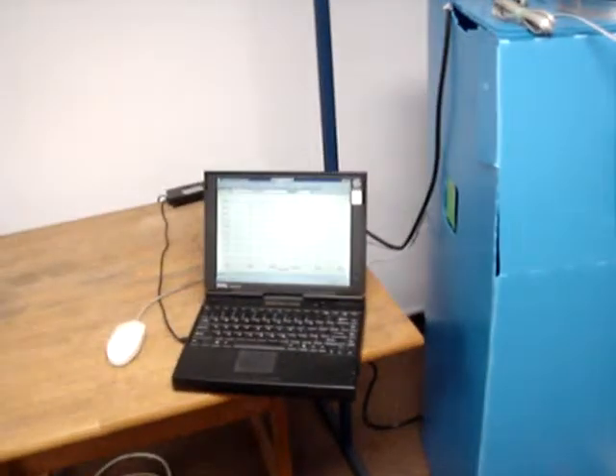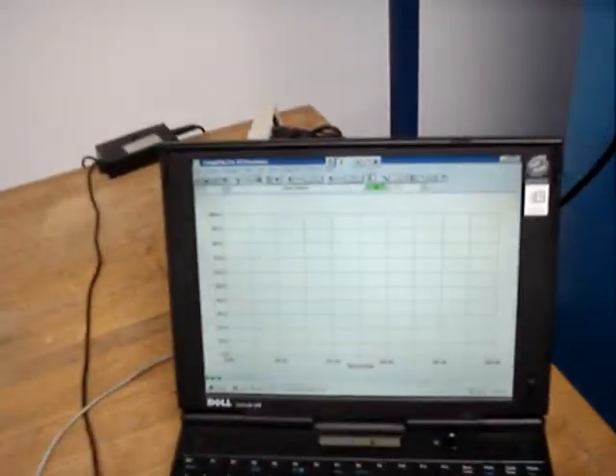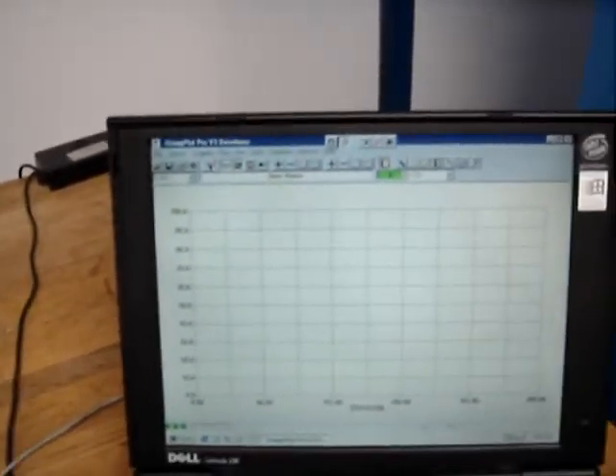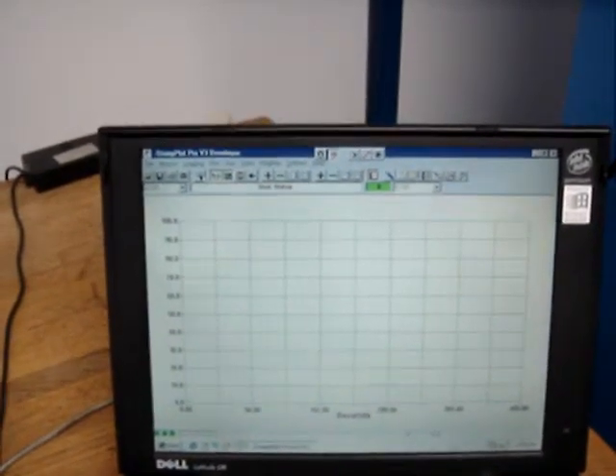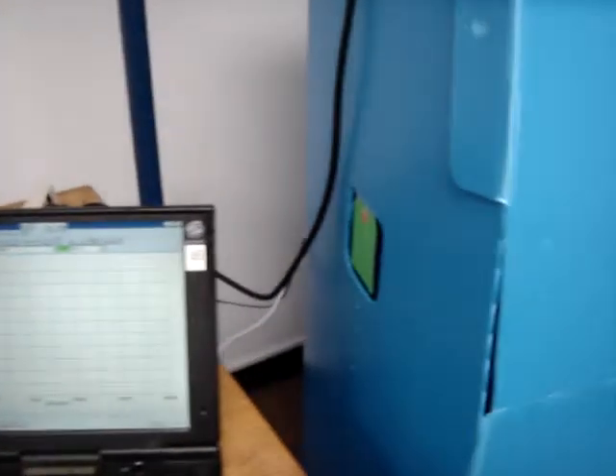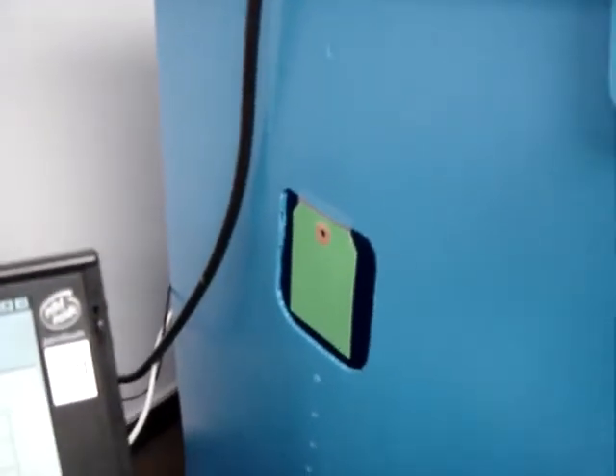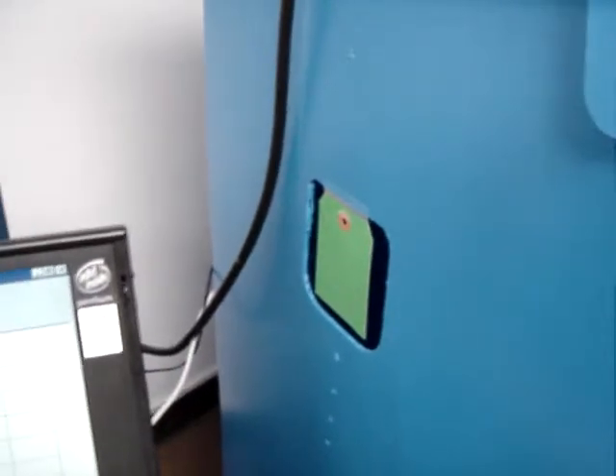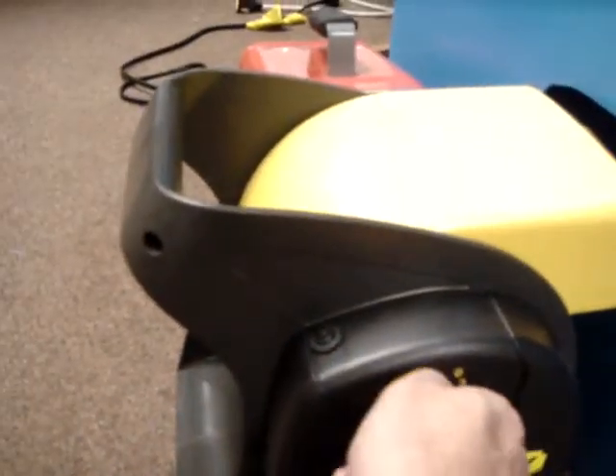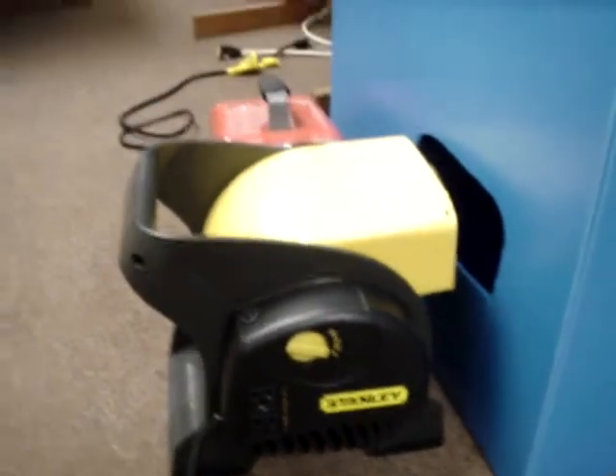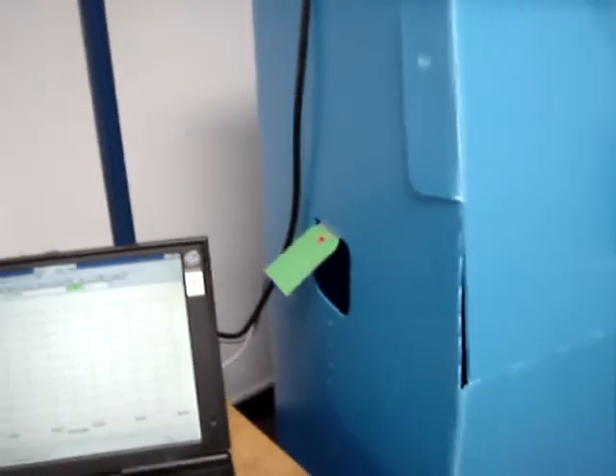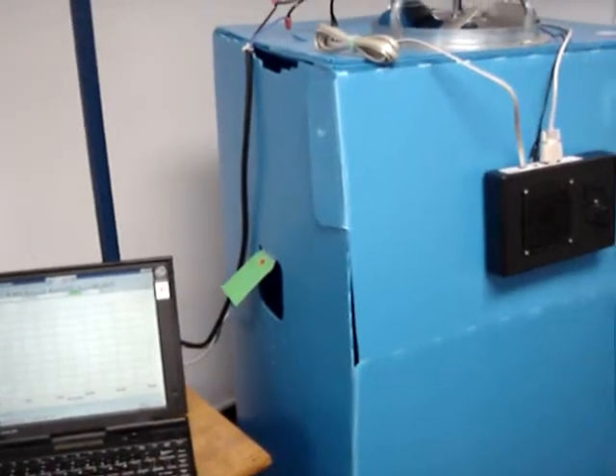And we have a laptop that is just used for plotting the speed of the fan. It shows speed as a function of time. And the little green flap there is going to show pressure inside the cabinet, whether the pressure is positive or negative. So, for example, if I turn the servers on, the airflow simulating the servers, that'll pressurize the cabinet, and you'll see that the green flap is showing that the cabinet's pressurized and air is being blown out of the cabinet.